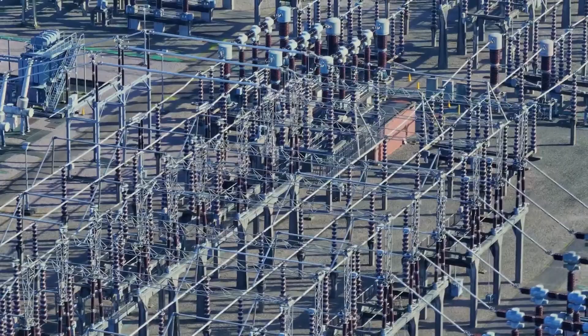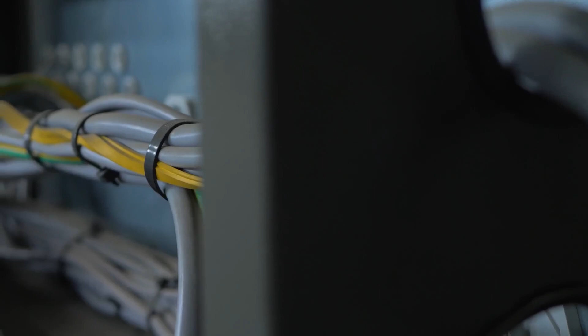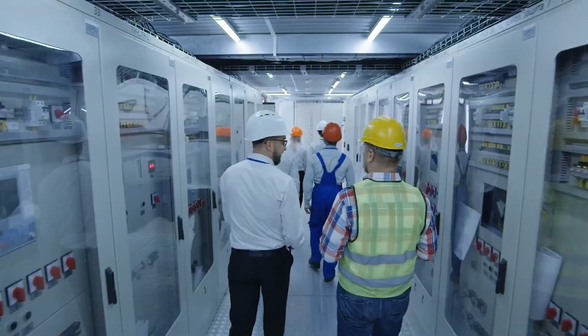Picture a single cable trying to carry that much current. It would need to be absurdly thick, and thick conductors radiate current unevenly, wasting power at the edges through a phenomenon called corona discharge. The engineering solution is to split the load across bundles of thinner conductors. Instead, the Changji Guquan line uses bundles of 8 separate wires per line, each roughly the thickness of a human wrist, working together instead of one massive single cable. It's the same logic as running 8 garden hoses side by side, instead of forcing all that water through one pipe wide enough to burst.